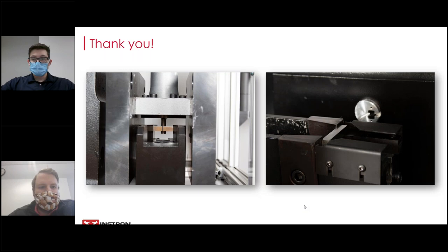Okay, great. So we had one question come in here while you were explaining the Charpy versus Izod, and the question was, do you get the same results from both tests? Yeah, for the most part, the result that you're obtaining is absorbed energy. Both of these tests give you that result. In determining whether to do Izod versus Charpy, number one is mostly the standard that you're testing to, but there are also some benefits. Again, it could be the hammer type. If you bought a C-shape hammer, you're going to be limited to Charpy. Or it could be if you're testing multiple specimens or specimen types like metal or plastic. Izod is common for plastic as well. But to summarize, absorbed energy is the result that you're looking for. Thank you.